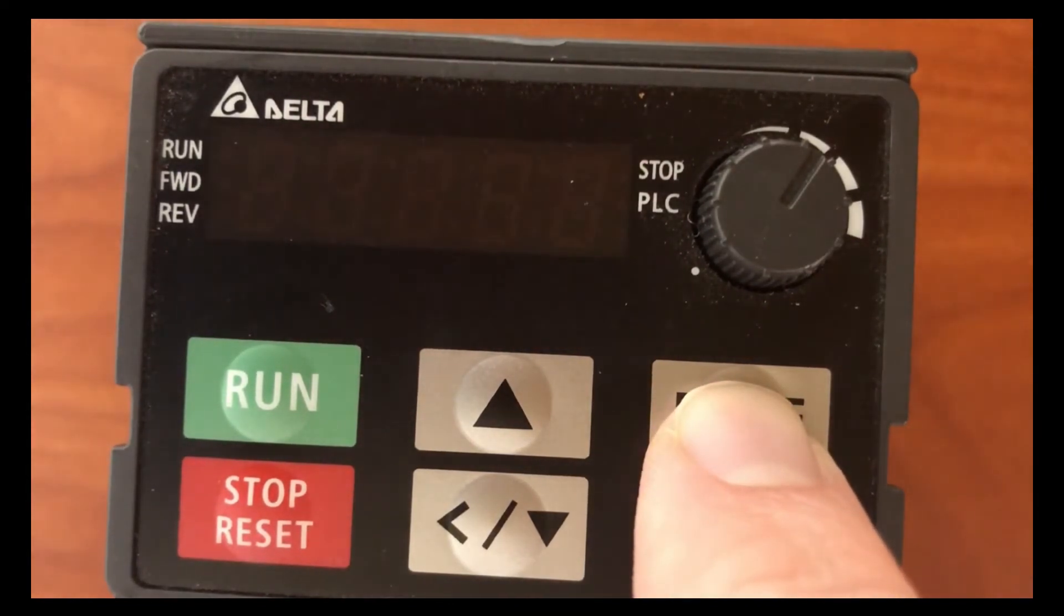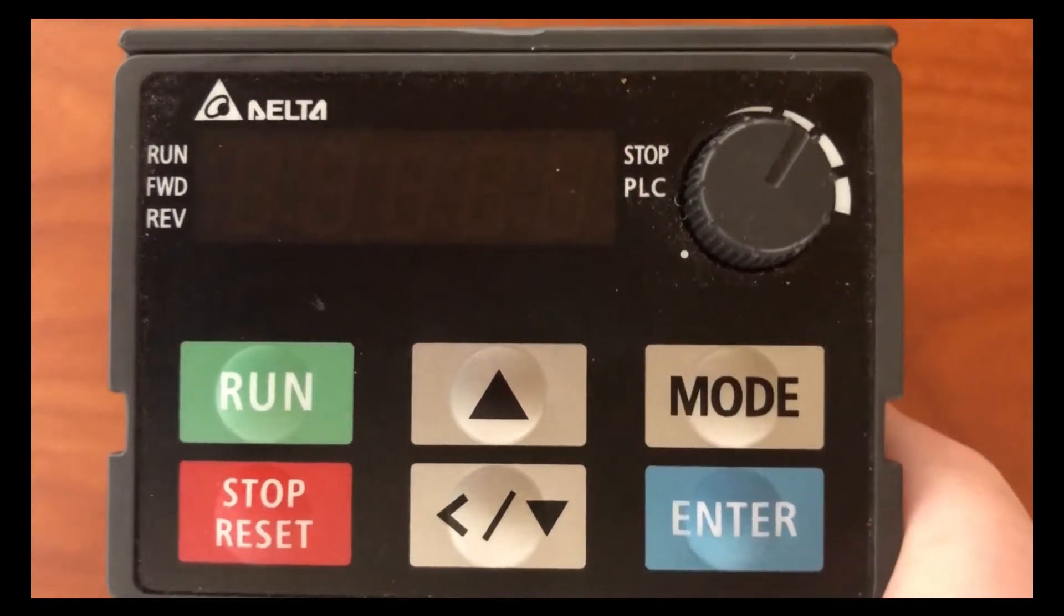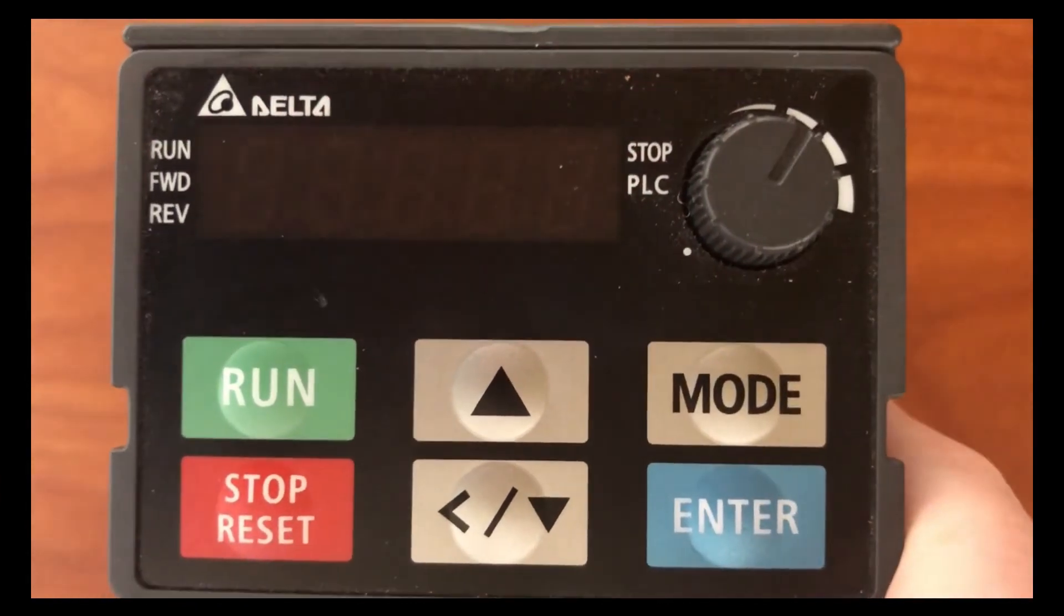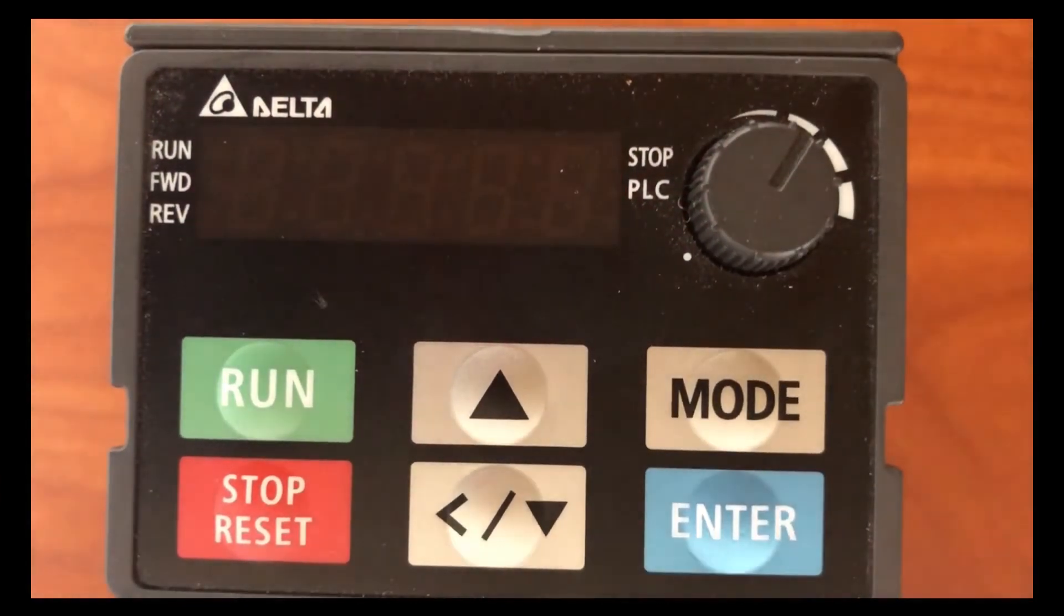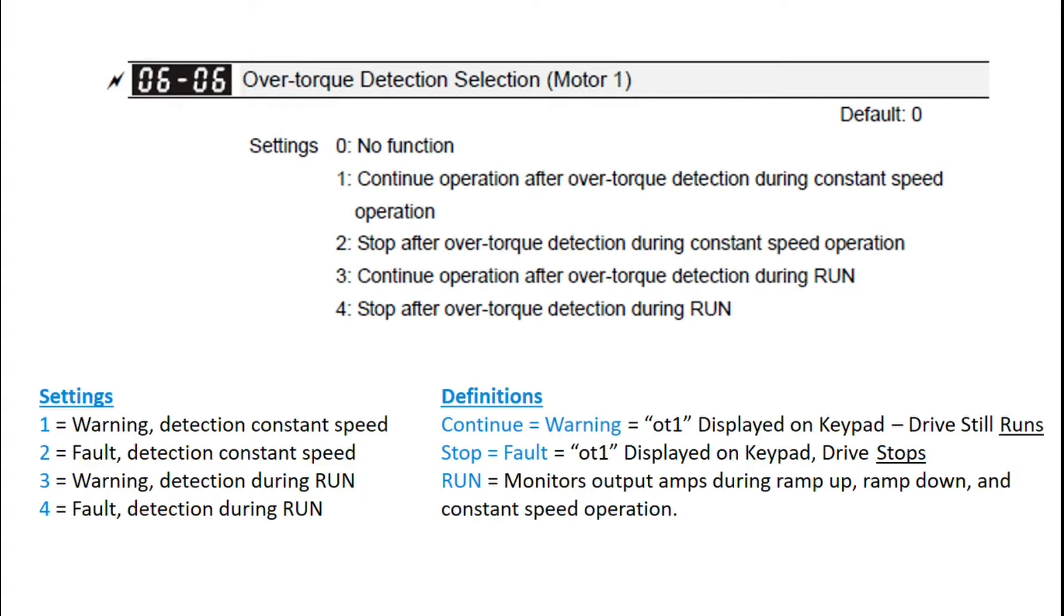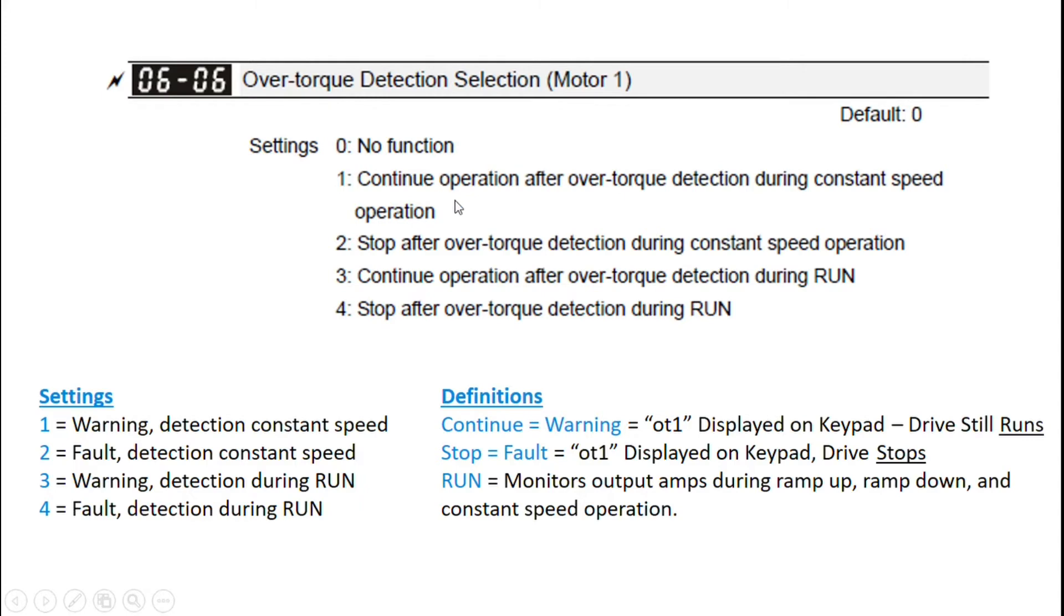And then I'm going to throw up a PowerPoint and go over what the different settings mean. Okay, so now I'm going to go into a little bit more detail about the over torque detection parameters. So 0606, this is your over torque detection selection, or it's the behavior that the drive is going to do if an over torque is detected.